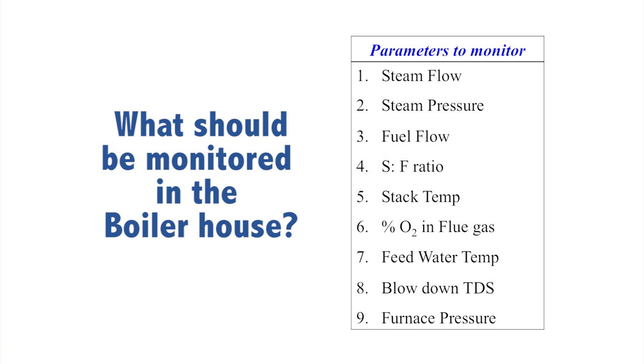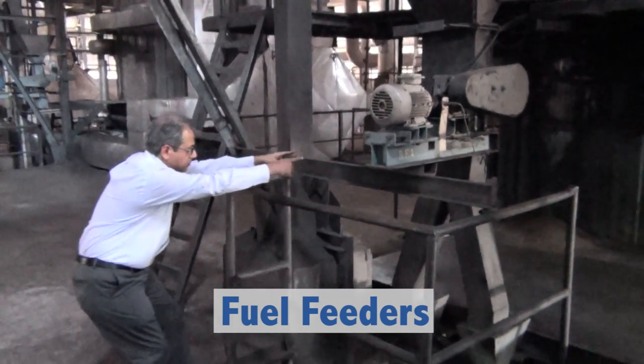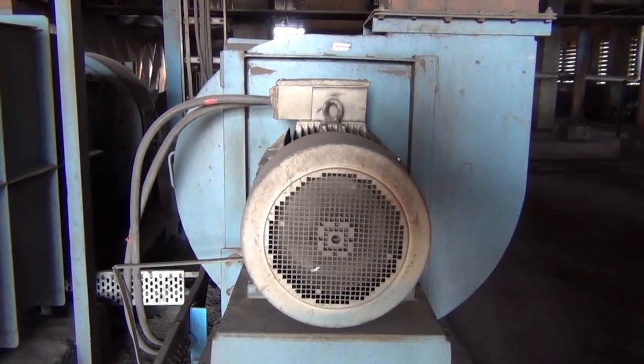In a plant, the steam load generally varies. As the steam load varies, the fuel feed rate also has to be varied to suit the steam demand. As the fuel feed rate varies, one has to correspondingly increase or decrease the FD fan air being supplied and the air sucked by the ID fan. Therefore, one has to look at a set of readings comprising the steam load, steam pressure, furnace pressure, oxygen level, and stack temperature. Looking at all this data enables one to determine the exact fuel feed rate, and once determined, the exact amount of air supplied for combustion by the FD fan can be set.